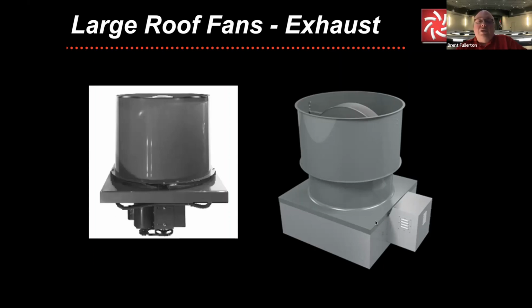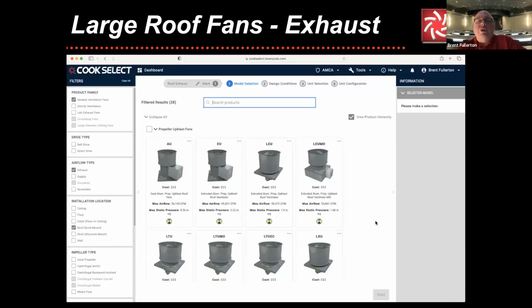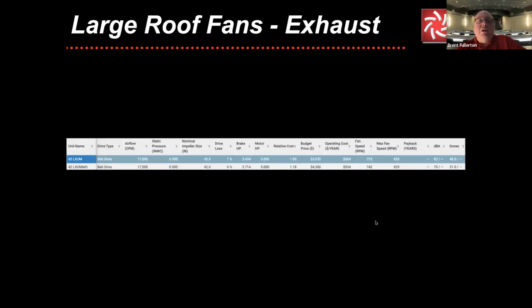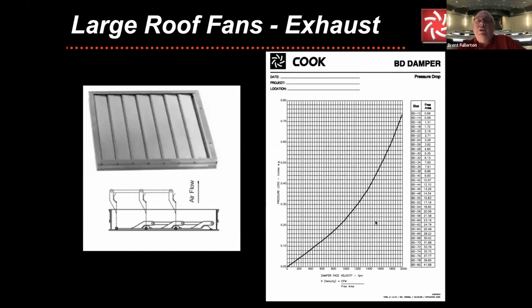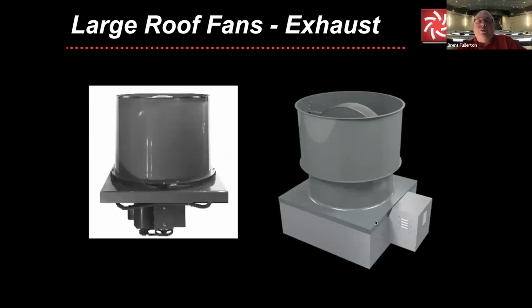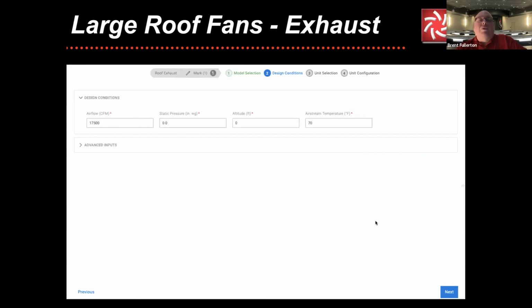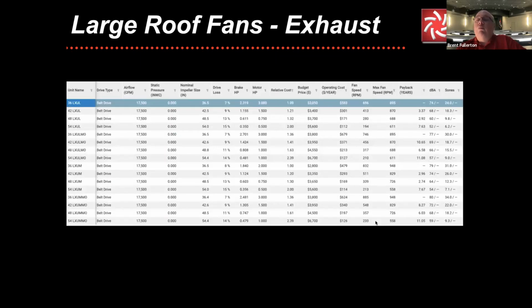The other thing is, notice the style on the left, you can service it from inside the building, where the product on the right has to be serviced from the exterior part of the building. So looking at several of these styles of products, we can zero in on one style versus another, but normally then we get into the point of using a backdraft damper. Now, a backdraft damper is impossible to use on the style of product on the left without a lot of difficulty, because then you couldn't get in to service the product from below. So I'm going to reselect this, taking a pressure out, because these are normally non-ducted and also are not installed with a backdraft damper. So now you get a lot more options.